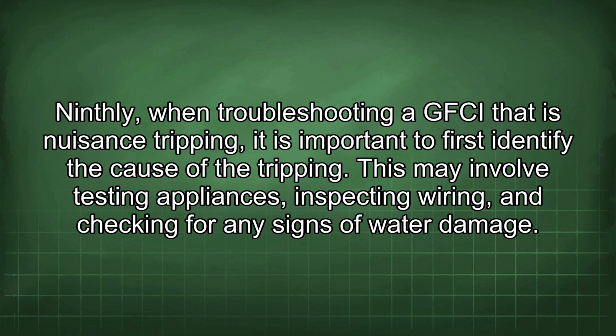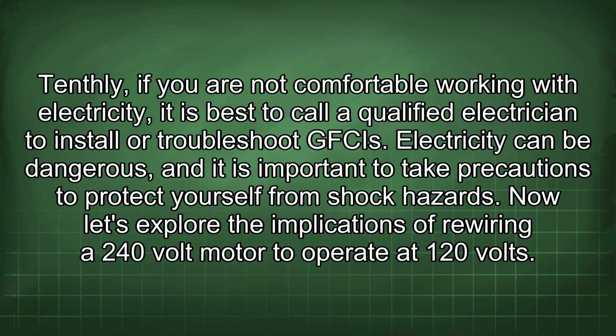Ninthly, when troubleshooting a GFCI that is nuisance tripping, it is important to first identify the cause of the tripping. This may involve testing appliances, inspecting wiring, and checking for any signs of water damage. Tenthly, if you are not comfortable working with electricity, it is best to call a qualified electrician to install or troubleshoot GFCIs. Electricity can be dangerous, and it is important to take precautions to protect yourself from shock hazards.